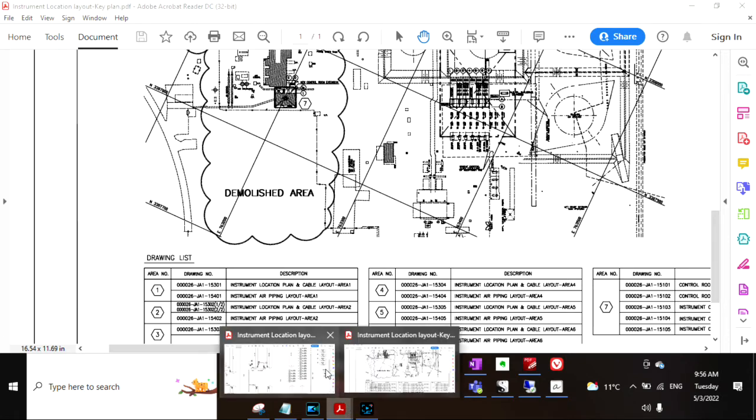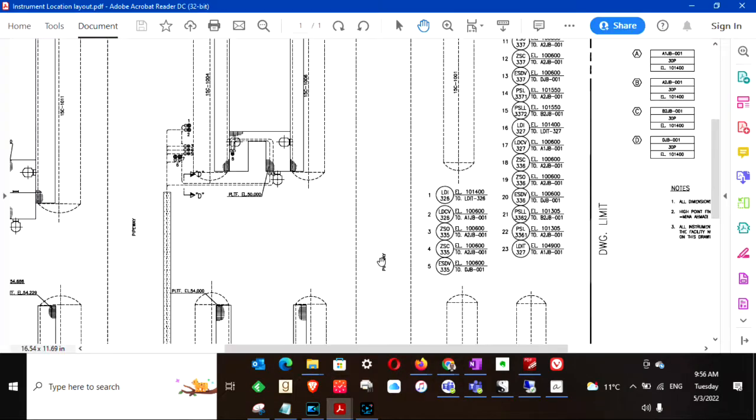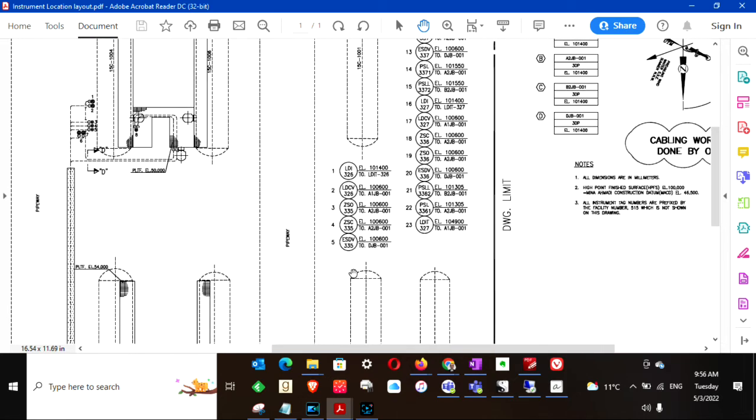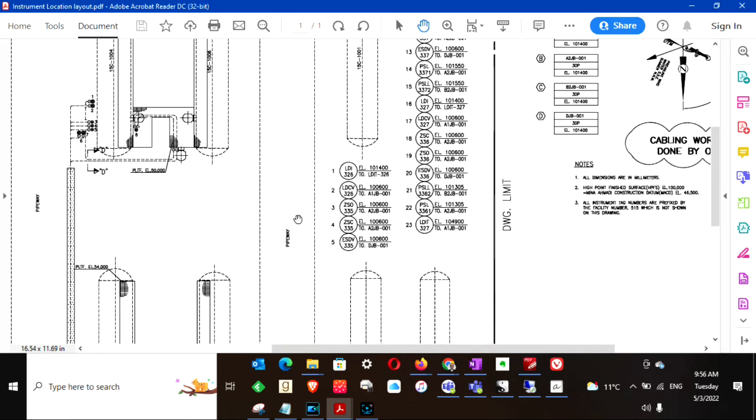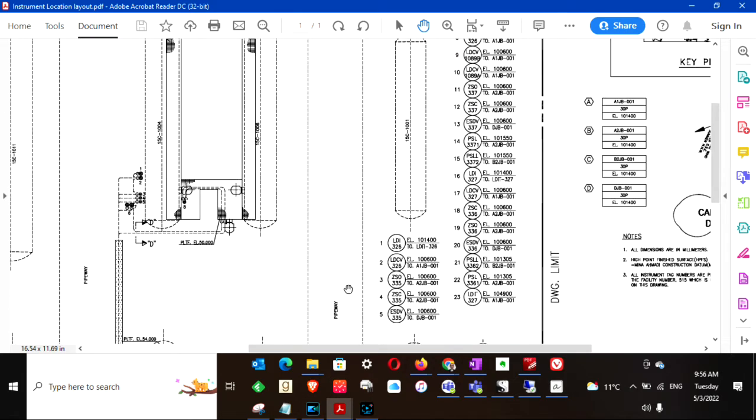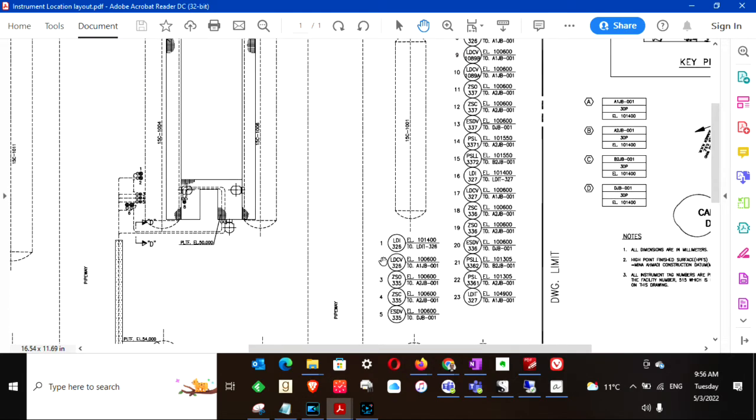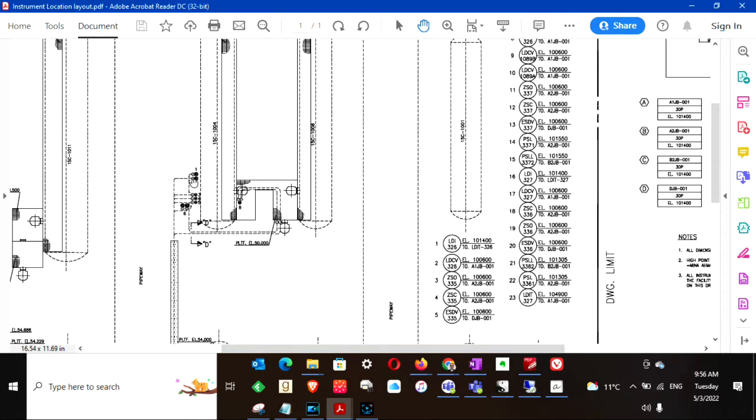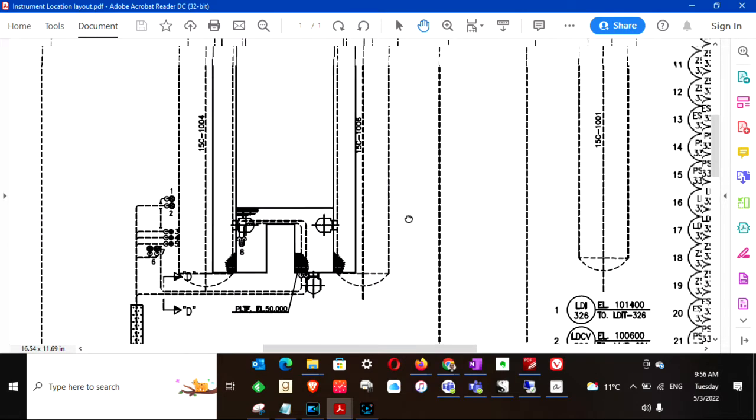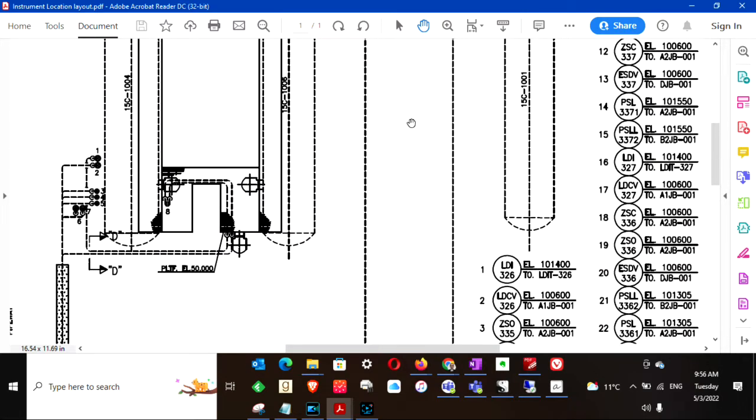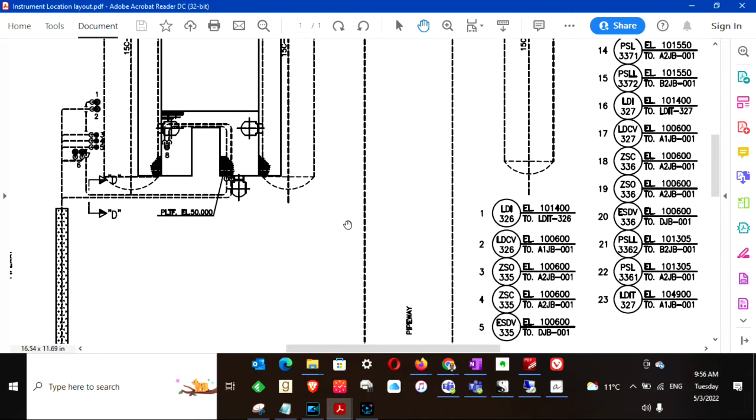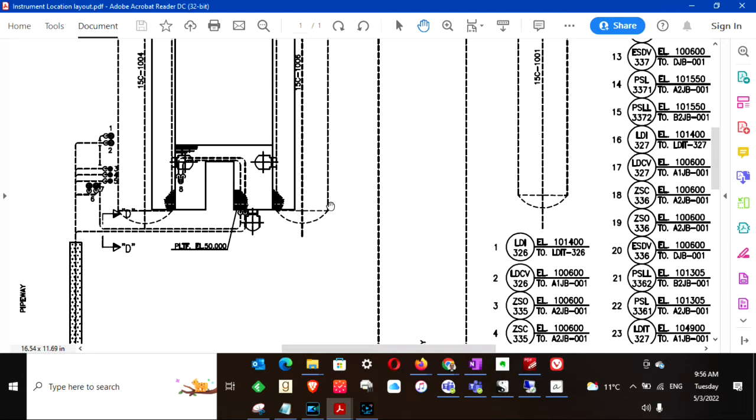And now, this is the instrument location layout which shows the location of instruments with respect to the equipment. For example, this number one instrument is this LDI 326. It shows its elevation also. With the help of instrument location layout, we will be able to plan for the tray and the various supports.